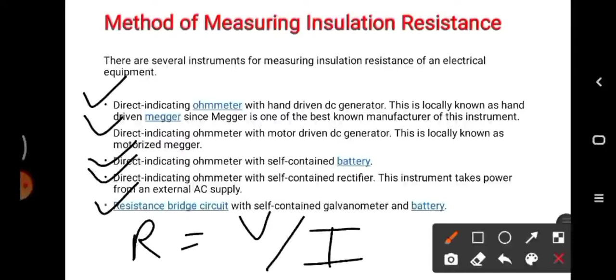When insulation resistance is measured with the help of DC supply, we take voltage and current readings with a DC voltmeter and DC ammeter. Insulation resistance is then measured as the ratio of voltage divided by current, where V is the voltage applied across insulation and I is the corresponding current flowing through it. When we use indicating instruments like a megger or ohm meter, the probes or leads of the instrument are directly connected across the insulation. After driving the instrument, the value of insulation resistance is indicated on the dial. In both cases, insulation resistance is measured at a standard time delay to get an accurate and error free reading.